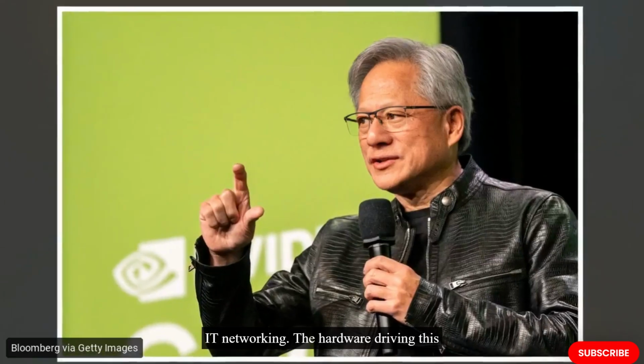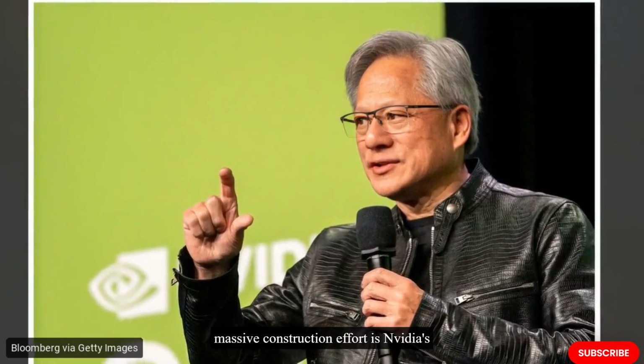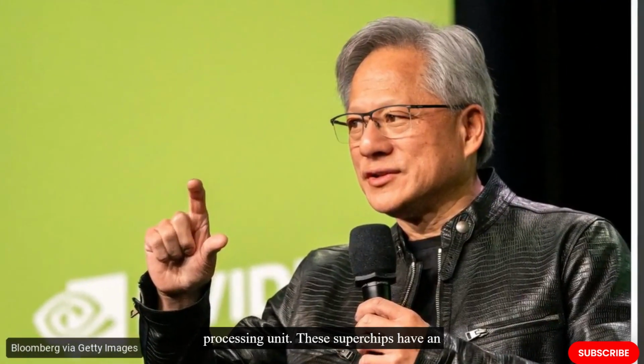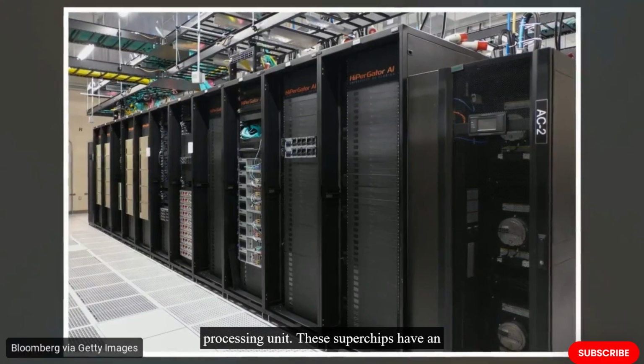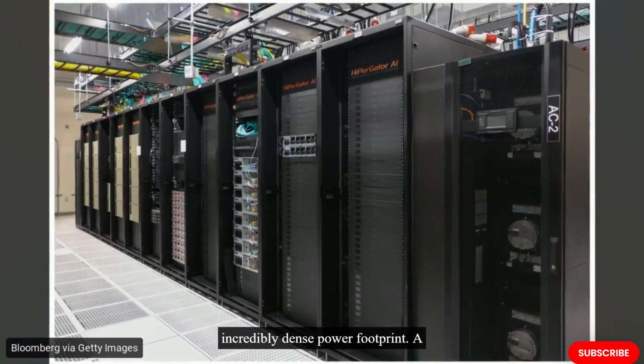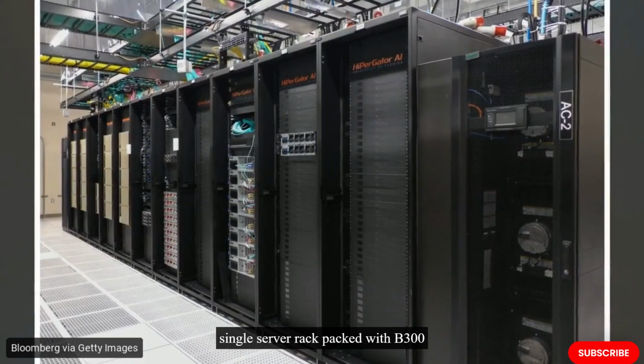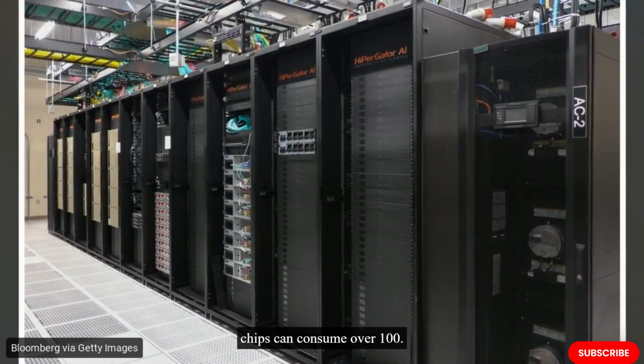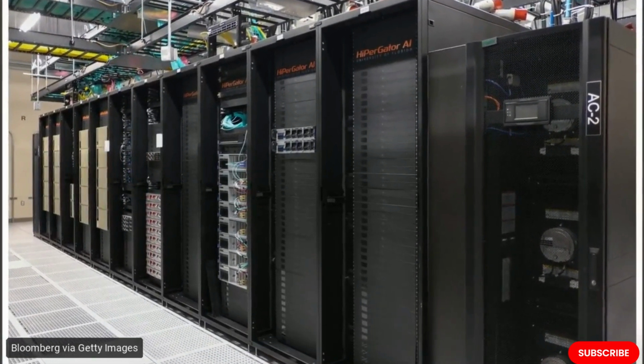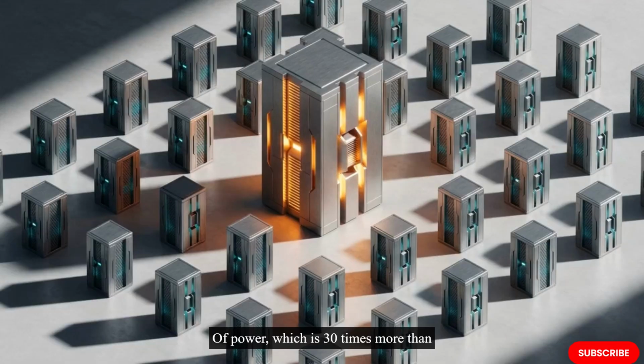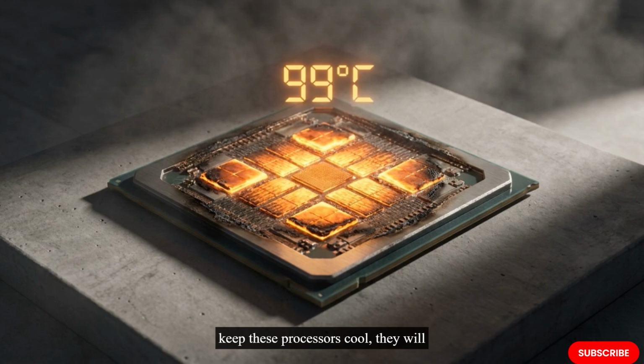The hardware driving this massive construction effort is Nvidia's next-generation B300 Blackwell graphics processing unit. These superchips have an incredibly dense power footprint. A single server rack packed with B300 chips can consume over 100 kilowatts of power, which is 30 times more than a traditional server rack. If you cannot keep these processors cool, they will reach dangerous temperatures and slow themselves down to prevent permanent damage.